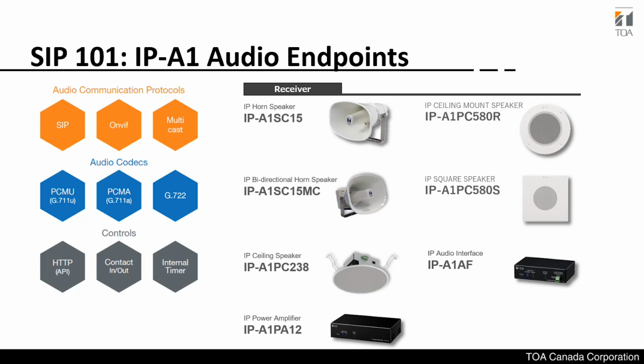So, a brief explanation of what multicast IP addresses are. They're kind of hidden IP addresses that are specifically used for multicasting. Each network switch has these multicast IP addresses pre-programmed. Here is how it works. Instead of calling each individual IP speaker using unicast, which will overload your network very quickly if you have hundreds of speakers, you're calling only the paging gateway, IP-A1PG.